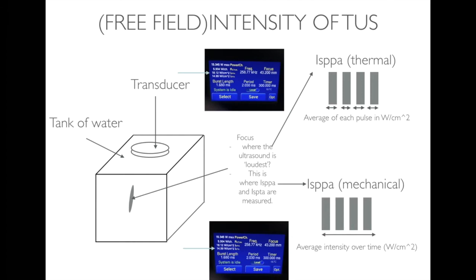There are two things you really need to think about to understand the intensity of transcranial ultrasound. You need to think not about the intensity as in the power of the transducer, but about what's going on in the acoustic focus. We're measuring the intensity in the acoustic focus, not the power of the transducer. That's important because what we want to think about is what the intensity is within the cortex, rather than what the intensity is within the transducer itself.